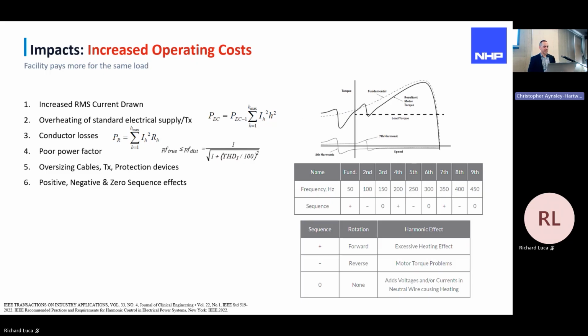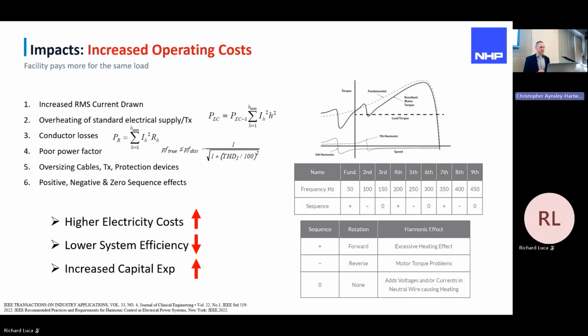Another aspect is the positive, negative, and zero sequence effects. So each order harmonic is given a sequence. Now, without going too detailed into it, 50 hertz is a positive sequence. It's rotating in a forward direction. The second harmonic is rotating in the opposite direction, whereas the third harmonic has a zero effect. So what that means for your system or your plant is you've got excess energy in the system rotating forward. The reverse effect you can see in the load torque of the motor. If we're introducing harmonics in the system, it's affecting the load torque of your motor. So in the resultant load torque, you can see the dips and the peaks there. So that's actually changing the magnetic fields in the motor. The zero sequence: those currents in the 3 phases all add up in the neutral. So that's not ideal. So overall for the facility, we're looking at higher electricity costs, lower system efficiency, and increased capital expenditure.